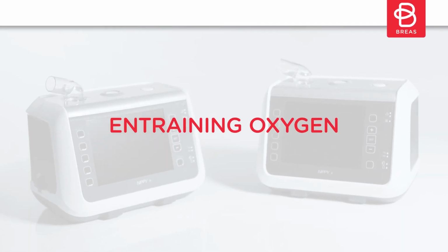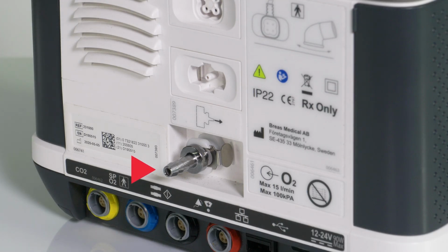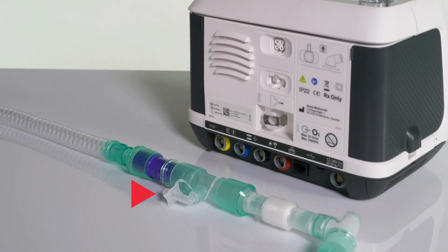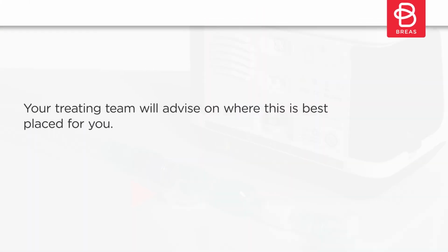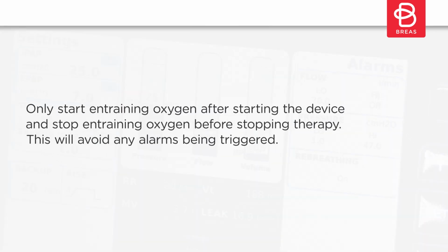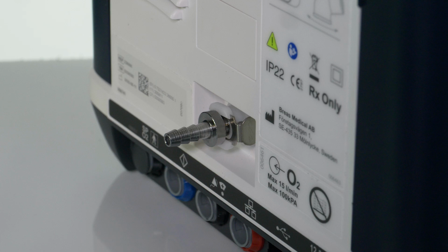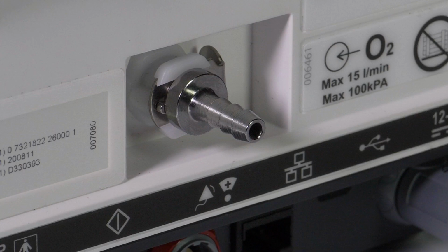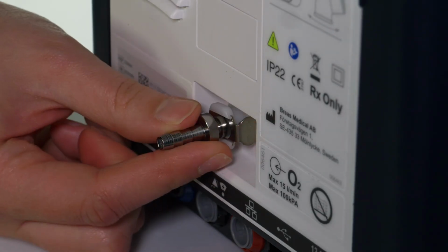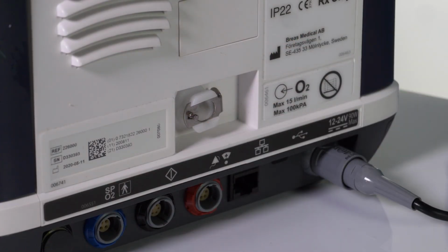Entraining oxygen. Oxygen may be entrained either into the rear of the device or via a connector within the circuit. Your treating team will advise on where this is best placed for you. Only start entraining oxygen after starting the device, and stop entraining oxygen before stopping therapy. This will avoid any alarms being triggered. The connector at the rear of the device should only be in place if oxygen is being entrained to prevent dust being actively pulled into the device when uncovered. To remove the connector, press the trigger latch on the left-hand side of the oxygen inlet, and it will release from the back of the ventilator.